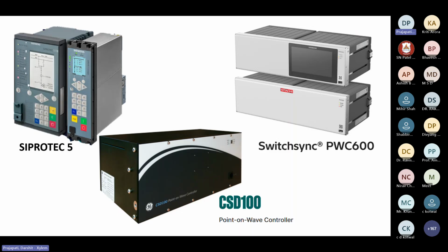So it is smooth. Not only the contact, but also the other components of the breaker will have less stress, like an SF6 breaker. It will have low degradation in quality, so the life of the SF6 gas will be increased. At every operation, there will be degradation in the quality of the SF6 gas, and after some cycles it is required to refill the SF6 as a routine. By introducing this kind of control switching technique, the degradation of the gas is reduced, the pressure is maintained for a long time, and the refilling cycle is also reduced.